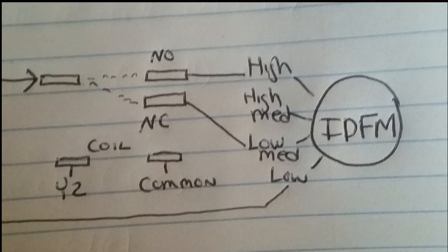If you look up on the top, you have the cooling tap, which is 120 volts going into the first terminal. On top, you have a normally open, which means it does not have voltage when the coil is not energized. That's going to high speed. You have a normally closed, which is energized when the coil is not energized, going to low medium speed. I'm using a 4-speed motor. Could be 3-speed, could be 5-speed, could be any amount of speeds.